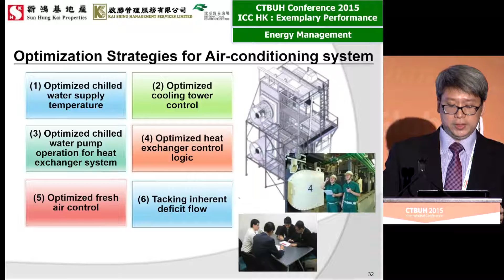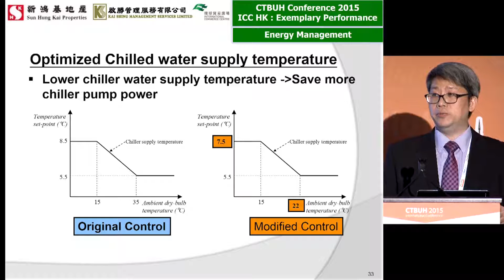Optimize chilled water supply temperature. Raising the chilled water supply temperature can reduce chiller power consumption, but on the other hand, increase pump power consumption. As ICC is a super tall building consuming a significant amount of pump energy, delivering water throughout the building, our optimal temperature not just enhances the energy performance, but also avoids valve hunting under the low load condition in winter.